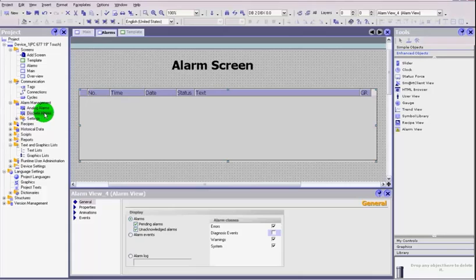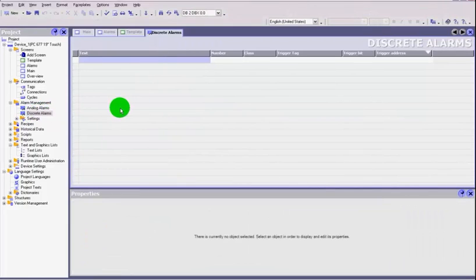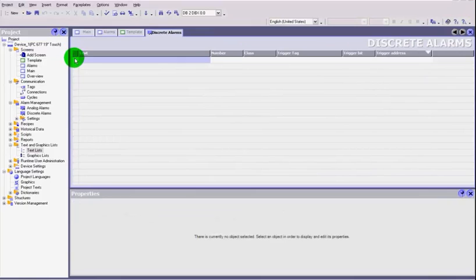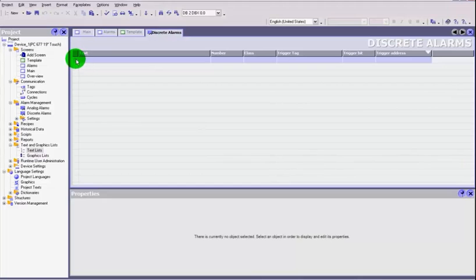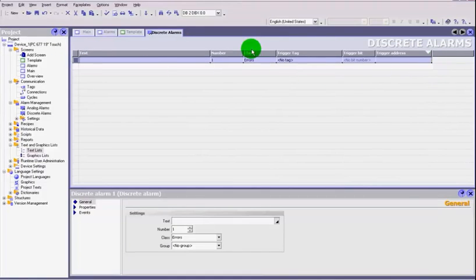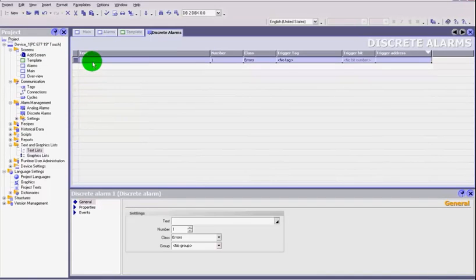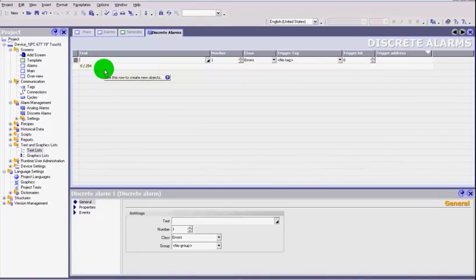We've created our alarm object, but we have to create our alarm messages. Go to alarm management and we'll deal with discrete alarms — analog alarms will be for another video. Double-click discrete alarms and you get a page very similar to your text lists from a previous video. Double-click in the top corner to create an alarm; it gives it an ID number and increments as you add more.